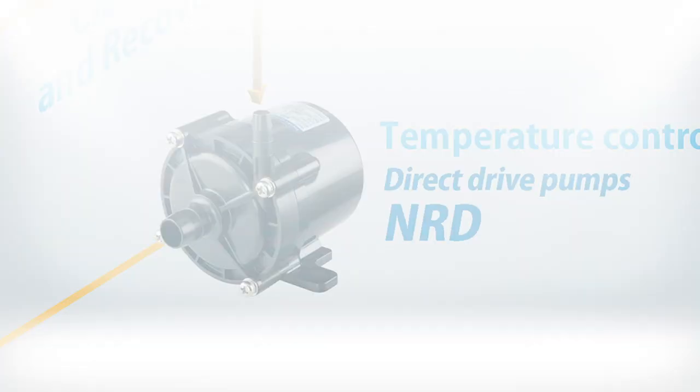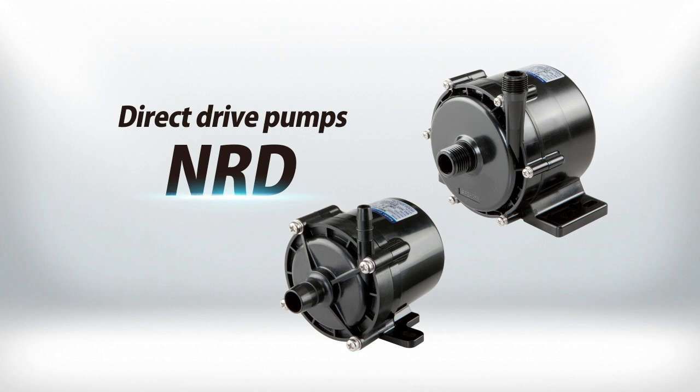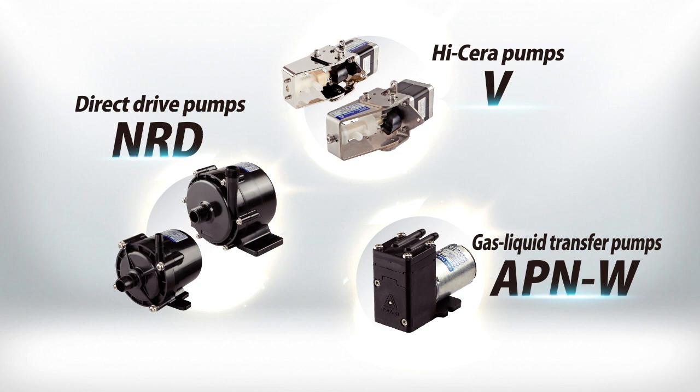The NRD canned pump is compact and incredibly durable. In combination with a heater or Peltier cooler, it manages the temperature of the equipment. This array of pumps — each the right pump in the right place — combines individual strengths to support the operating precision of the automated clinical chemistry analyzer, contributing to safe and effective operation.